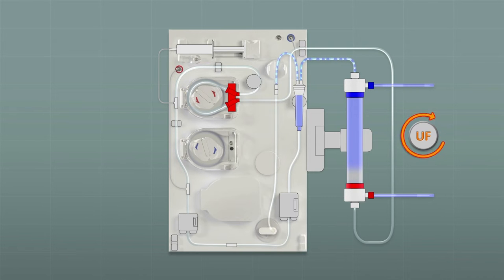Once the fluid reaches the drain port, the blood pump starts distributing the fluid throughout the bloodline to make it air free. Inside the venous chamber the air is separated from the fluid.